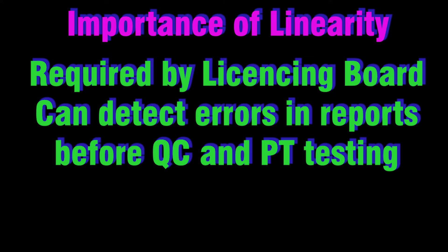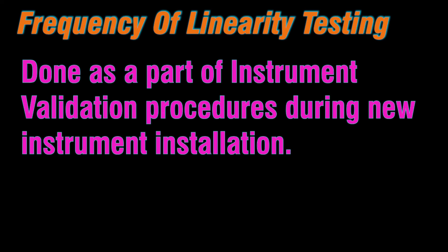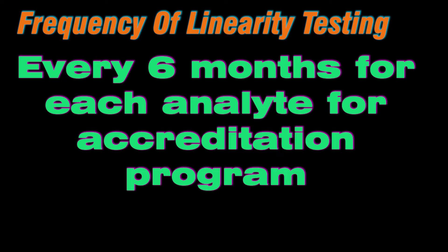Why is linearity or calibration verification important? It is required by the accreditation authority. If the calibration changes, the patient test result values will change. Linearity and calibration verification can detect problems earlier than quality control or proficiency testing. If the linear range does not cover the analytical measurable range, there may be a problem with the reagent, specimen handling, or analyzer, and adjustments to the reportable range may be needed to reflect the linear range.